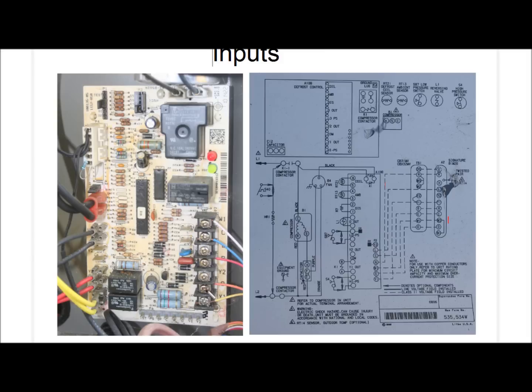The O terminal is for the reversing valve. In a heat pump, that reversing valve determines whether it's in the heating or cooling mode. So when 24 volts is applied, it energizes the reversing valve. When 24 volts is removed, it de-energizes the reversing valve. And again, this all comes from the thermostat inside the home via the air handling unit.